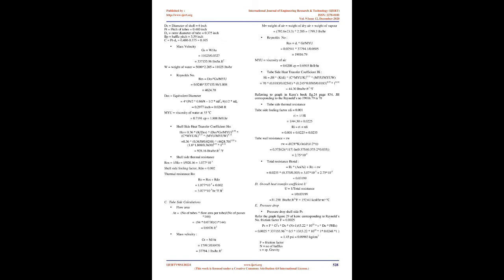Number of passes. To obtain greater heat transfer coefficient and also to reduce scale formation, number of passes is chosen to get the required tube side fluid velocity. The tube passes vary from 1 to 16. A single tube pass is selected for the design.